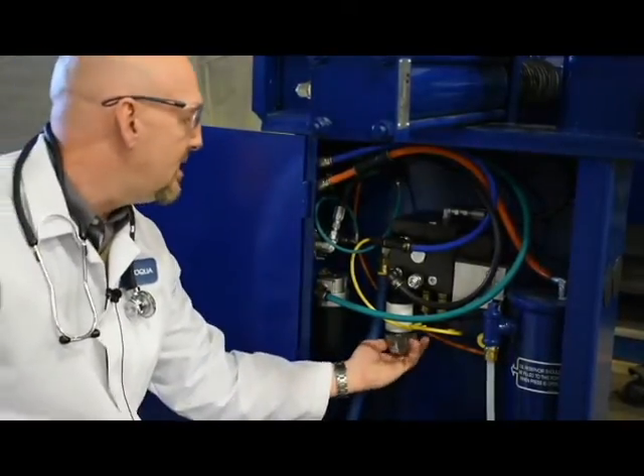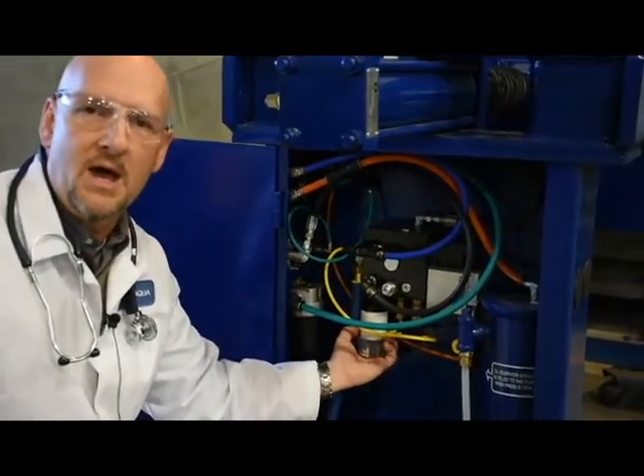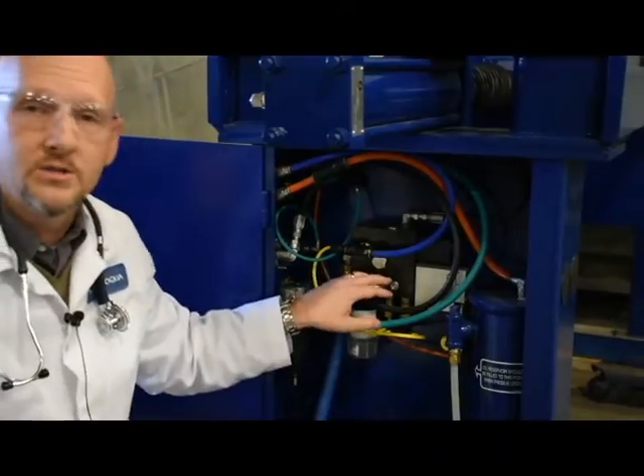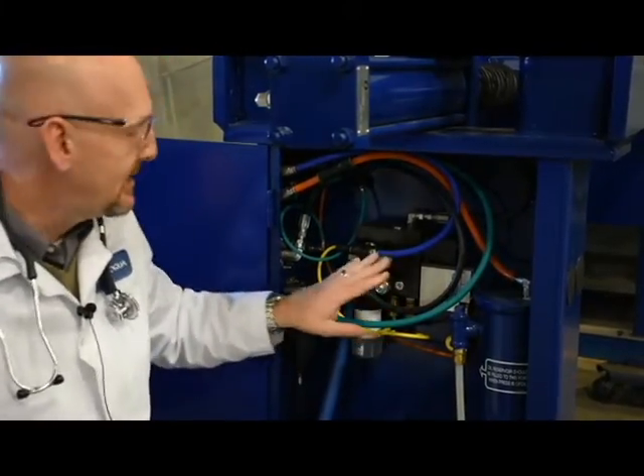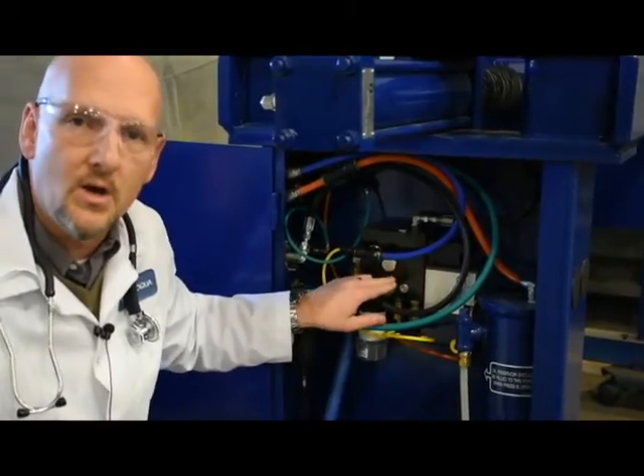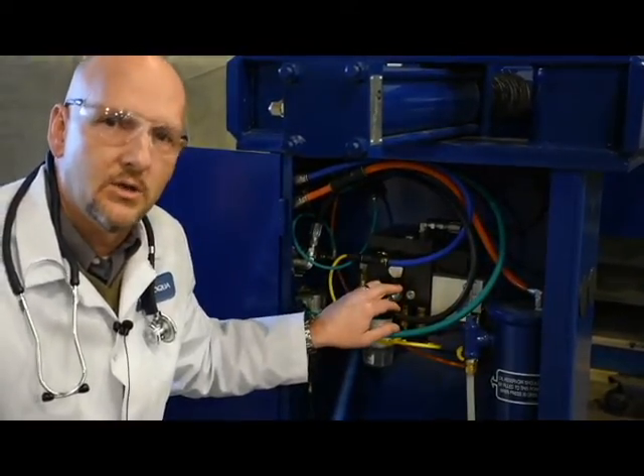So that's probably the three most common reasons why your pump would continue to run. Now keep in mind, if the pump is running and it's going across the relief or some other orifice, it's going to create heat. So a lot of times you can just put your hand on there and find out where it's leaking through. That'll help troubleshoot and get you to the right point.